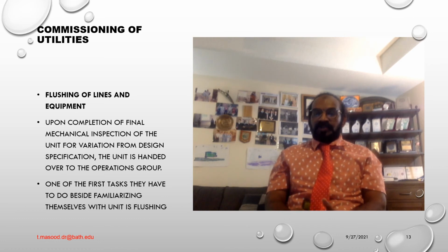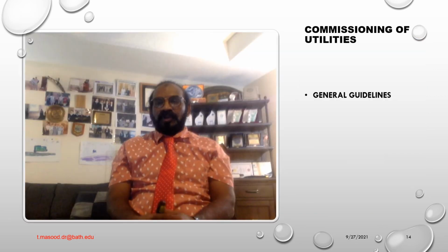In order to protect equipment and instrumentation during the flushing and blowing procedure, the flushed line must be disconnected from equipment. The instrument must be isolated. Orifice plates and valves must be dismounted. Next are the guidelines. Okay, commissioning of utilities, general guidelines.